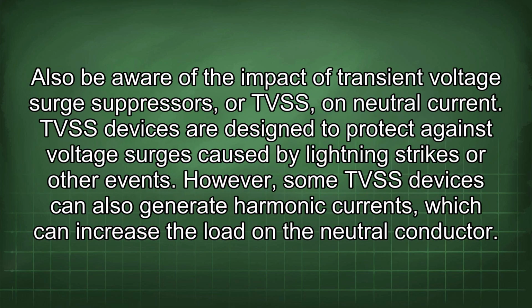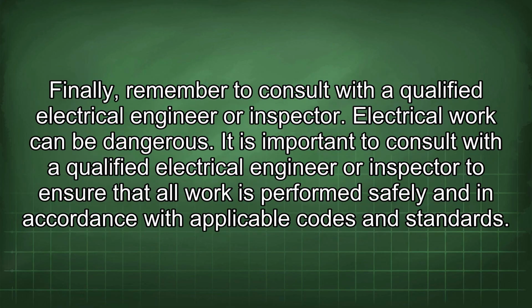Also be aware of the impact of transient voltage surge suppressors, or TVSS, on neutral current. TVSS devices are designed to protect against voltage surges caused by lightning strikes or other events. However, some TVSS devices can also generate harmonic currents, which can increase the load on the neutral conductor. Finally, remember to consult with a qualified electrical engineer or inspector. Electrical work can be dangerous. It is important to consult with a qualified electrical engineer or inspector to ensure that all work is performed safely and in accordance with applicable codes and standards.